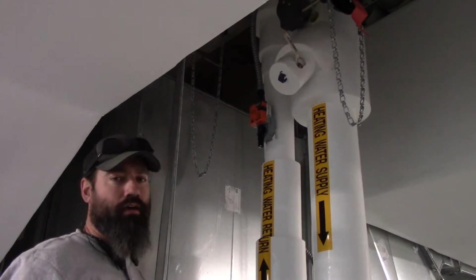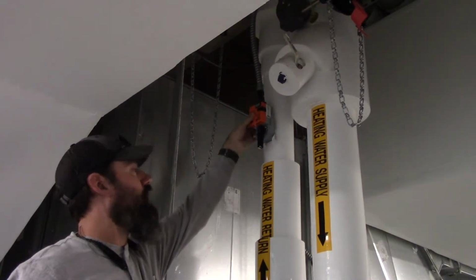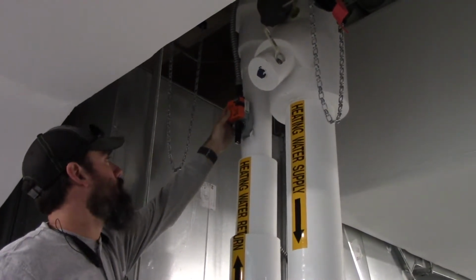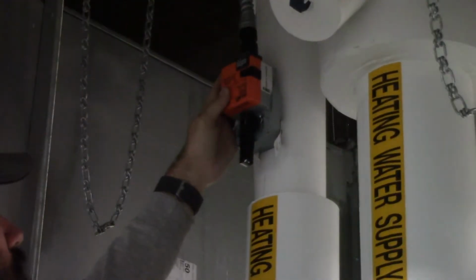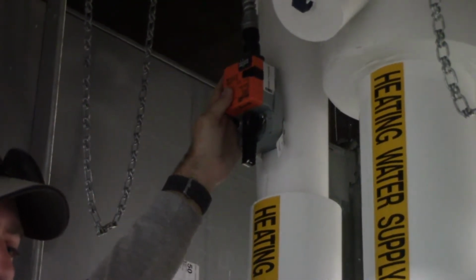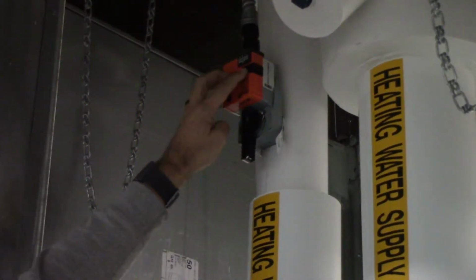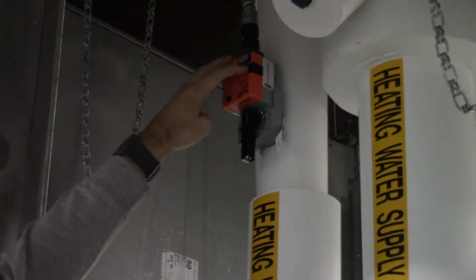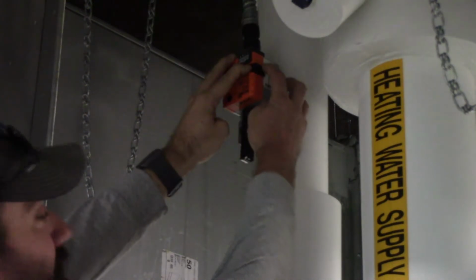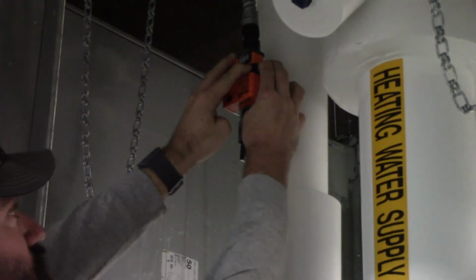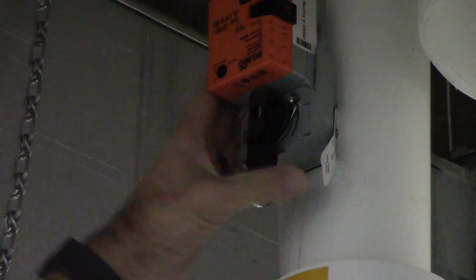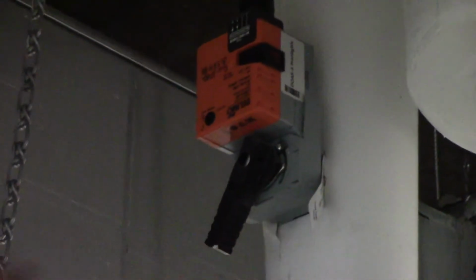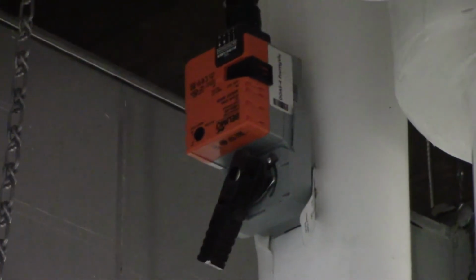Okay, all of your units have roughly the same hot water, chill water valve actuator. And they do their own thing most of the time, but you do have the ability to manually override them. So there's a clutch right here. It's this black button on the top of this orange cover. If you push that device in, and there's a little tab on the side, if you push that down, it'll lock this clutch in. And that will allow you to manually put this valve where you want, and it'll stay there as long as that clutch is in.